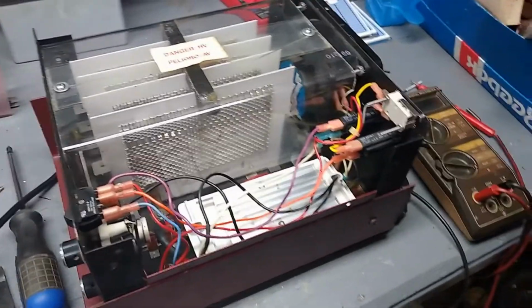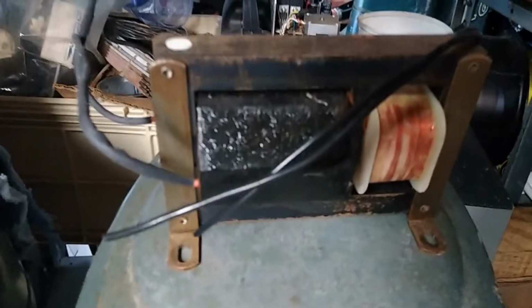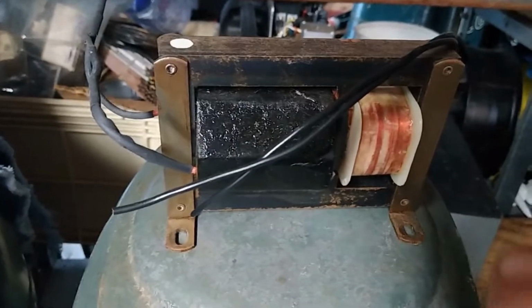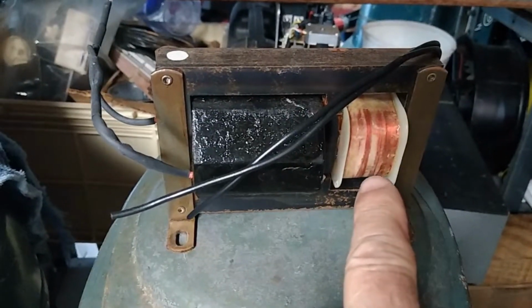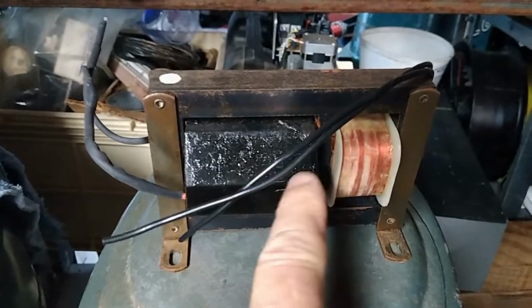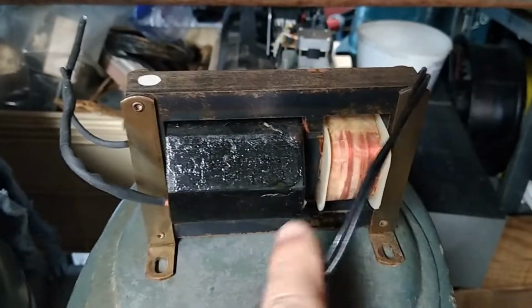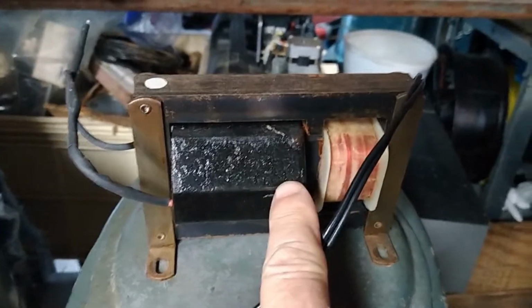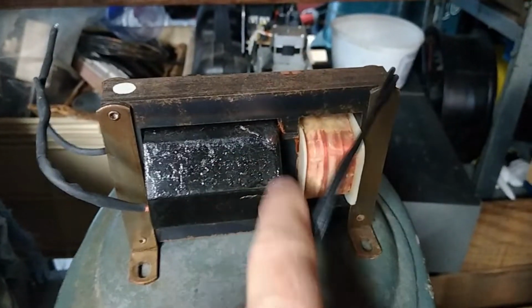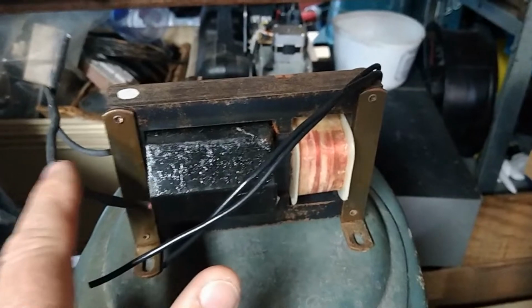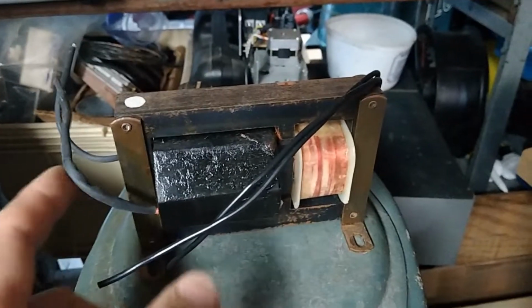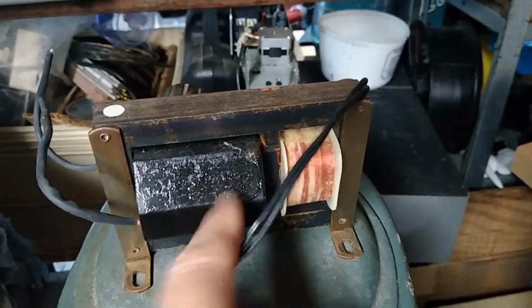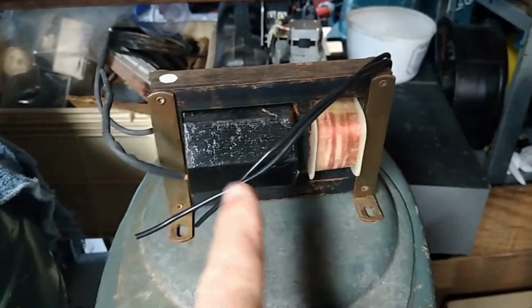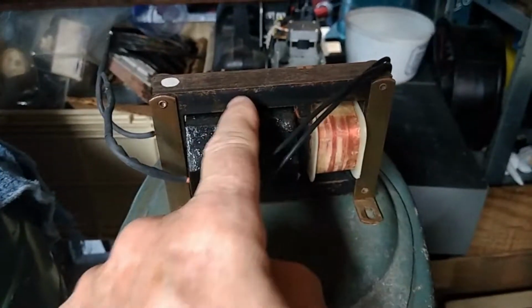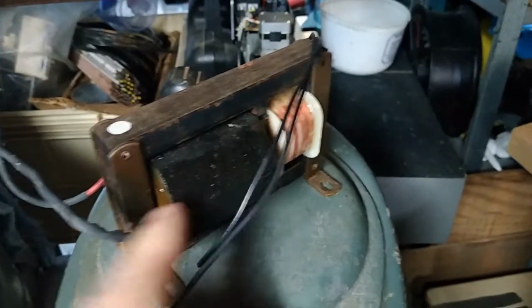After digging around a bit, I figured out the original transformer had gone bad. This is the AC winding, the high voltage winding, and it has multiple sections of fine wire. It was putting out a tiny bit of voltage, so one of these is open or shorted. You think I'm going to go look for one of those? No telling what one of these would cost if I did find one.